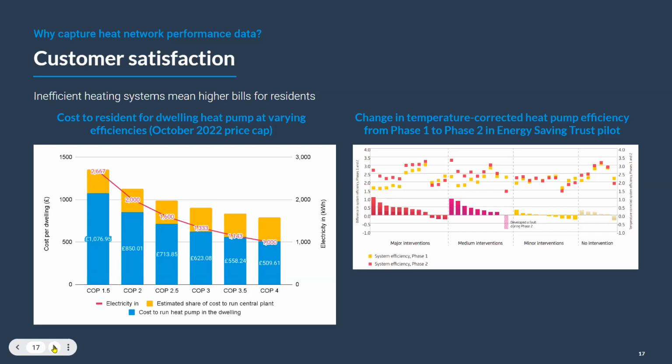For example, engineers turn up to site and make some small changes. That just adds and adds to the issues. Real-world monitoring of heat networks over a 3-year period, a project that we carried out with the UK government, showed that the cost of heat and carbon emissions can more than double on a heat network within 3 years if actions aren't taken. And to date, no detailed performance data from an ambient loop network has been published.